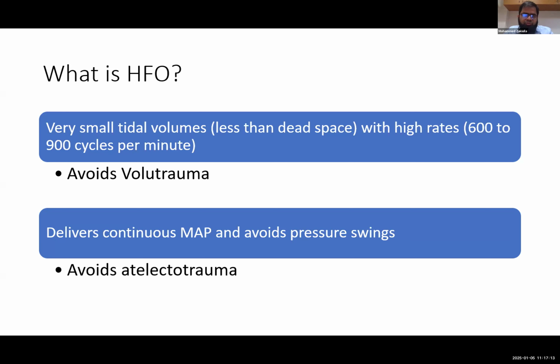And we also use very high rates. Normally we use around 10 to 15 Hz, that means 60 breaths per minute for each Hz. So 10 Hz means almost 600 breaths per minute. That's normal, but sometimes, depending on the underlying lung disease, you might use a frequency of 8 Hz also, that is around 500. So the basic concept is you are using very high rates and very small tidal volumes. This will avoid volutrauma, which has already been proven in the previous Cochrane reviews and systematic reviews.